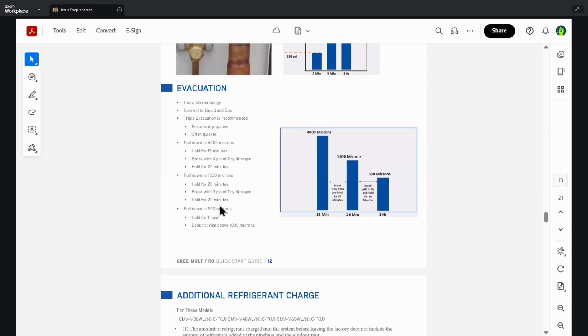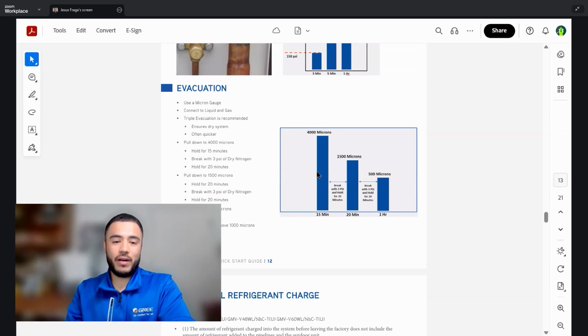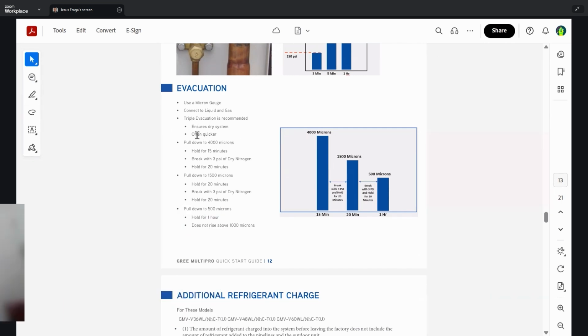The evacuation. So, you always use a micron gauge, because how are you going to know how many microns you have pulled down with your vacuum if you don't have a micron gauge? You can connect your liquid and gas, and perform a triple evacuation. It's always recommended. It always ensures that the system is dry, and it often is quicker once you do verify that you do the triple evacuation.